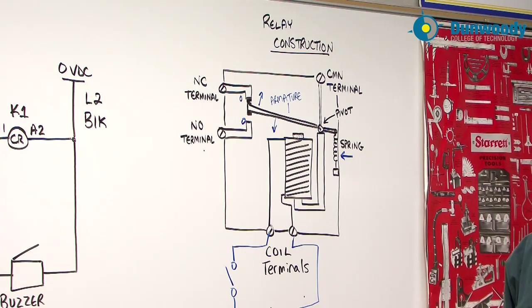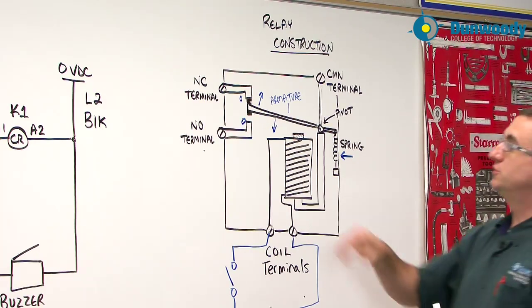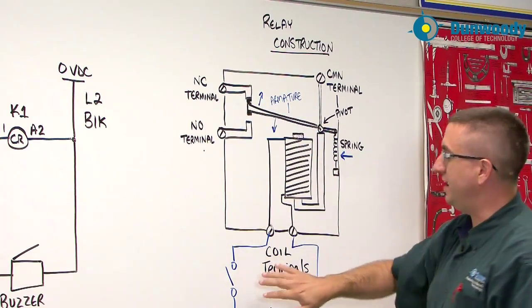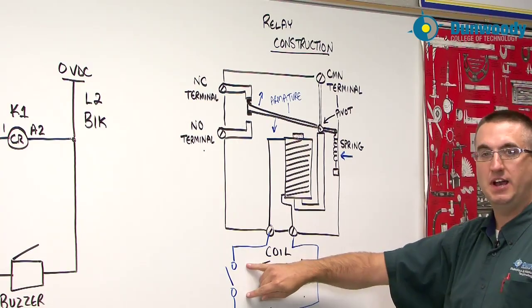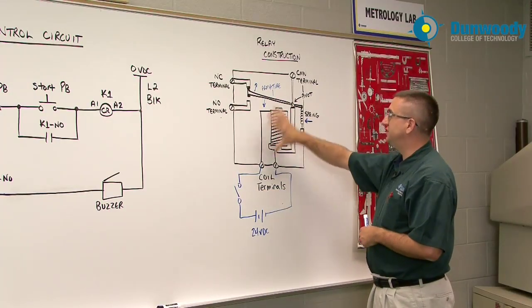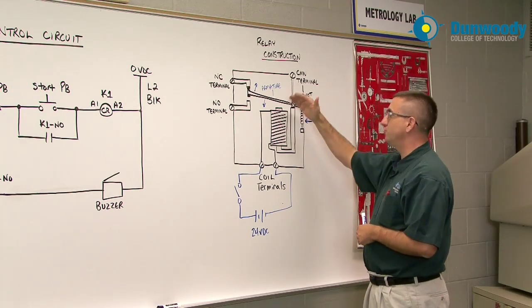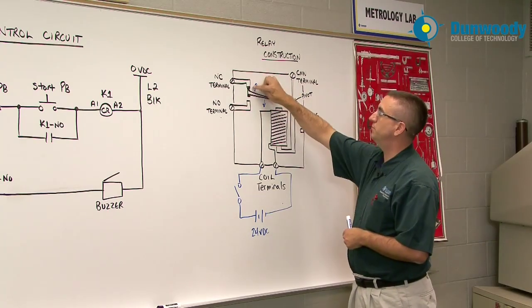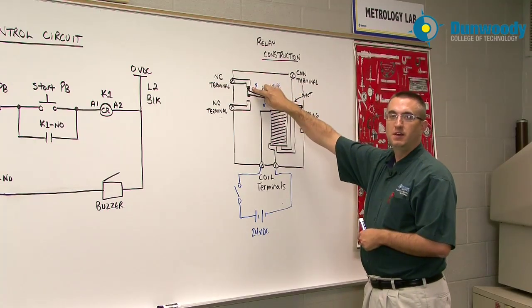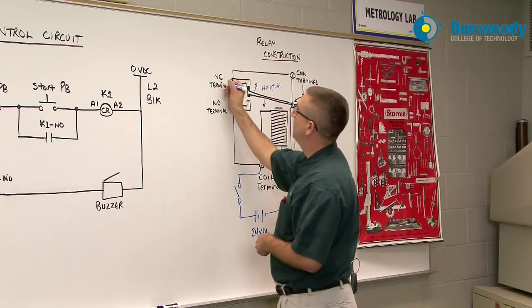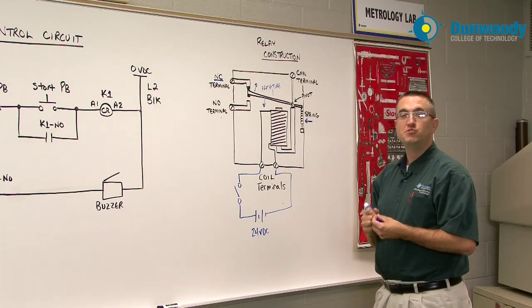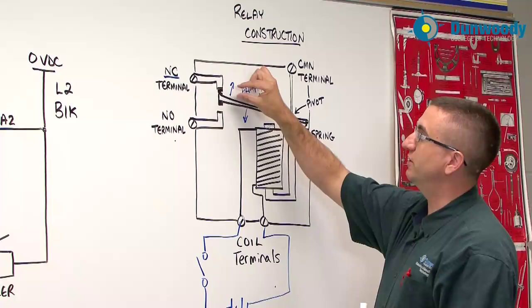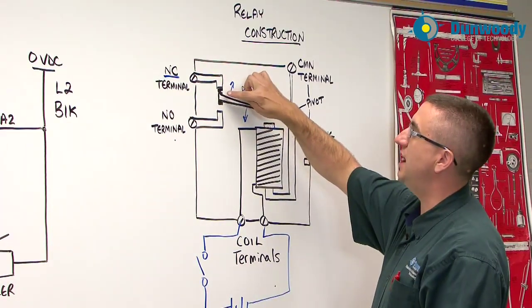These are what we call our normally open and normally closed contacts. So as I look at this drawing here, what I can see is right now my coil is de-energized. So the switch is off, the coil is de-energized, the spring is pulling on this. There's no magnetism to pull on the armature. And what happens is this armature flies up to the normally closed contact. And what normally closed means, this NC stands for normally closed. It means that it's normally closed without power on the coil. So in this particular example the armature is sitting on the normally closed contact.